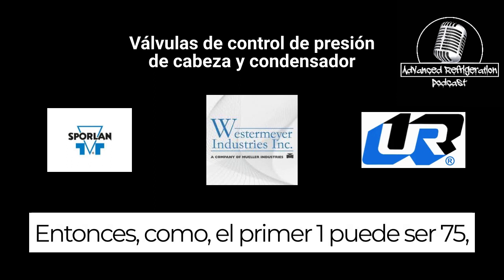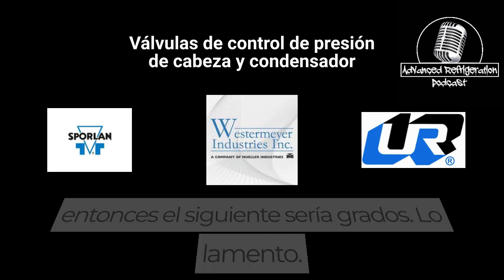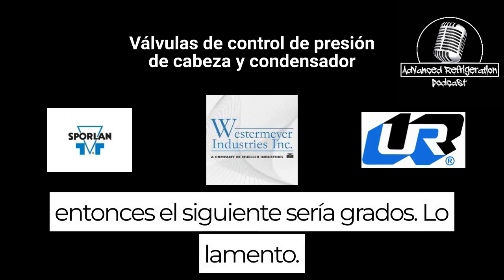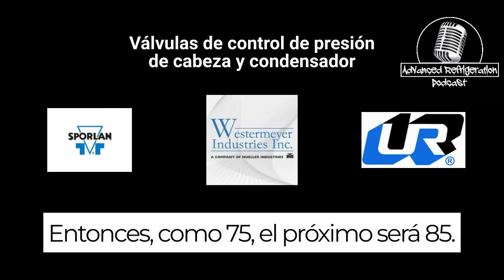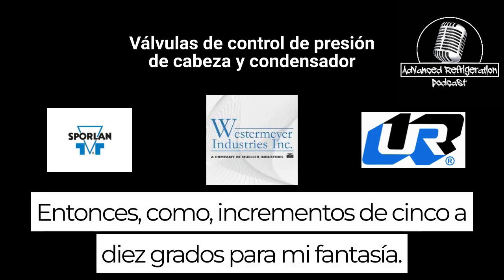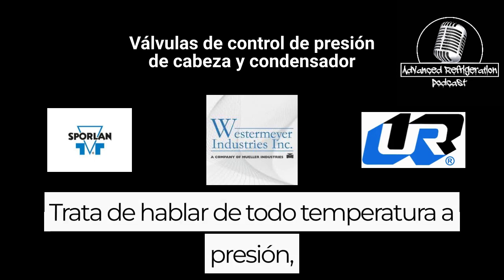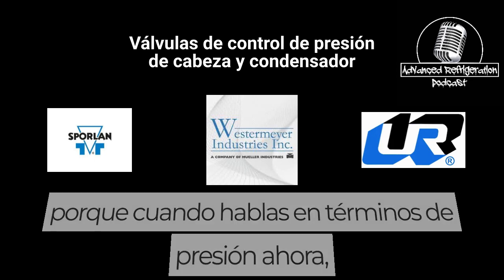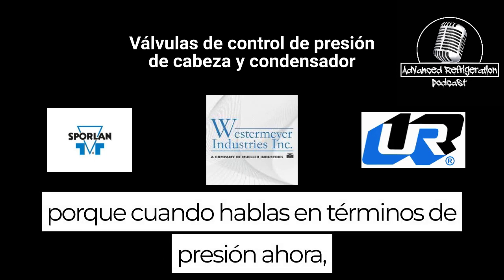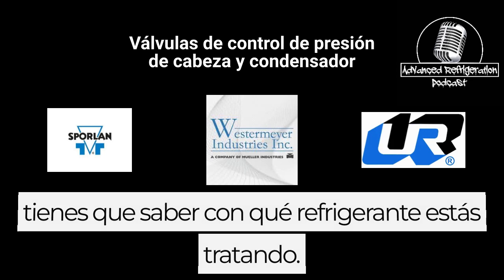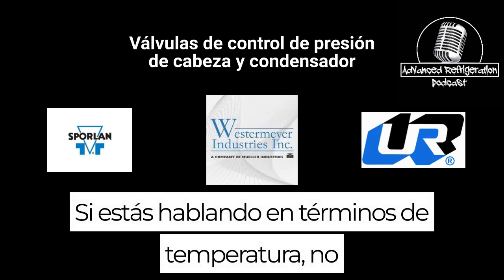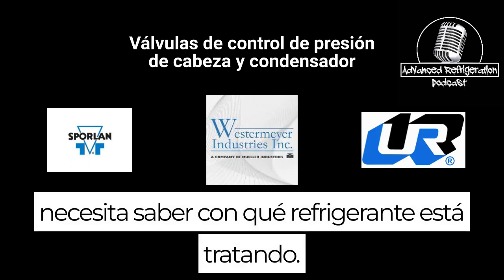So like the first one may be 75, then the next one would be 80, then 85. So like 5 to 10 degree increments for my fan cycling. Try to talk about everything in temperatures, not pressure, because when you're talking in terms of pressure, now you have to know what refrigerant you're dealing with. If you're talking in terms of temperature, you don't need to know what refrigerant you're dealing with.